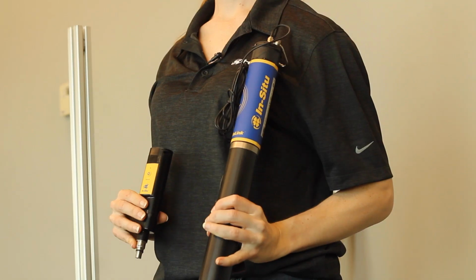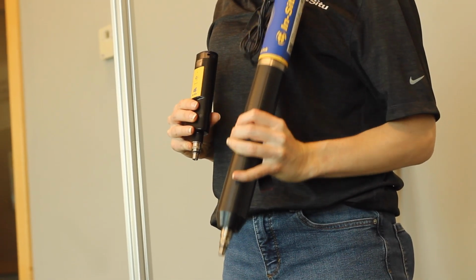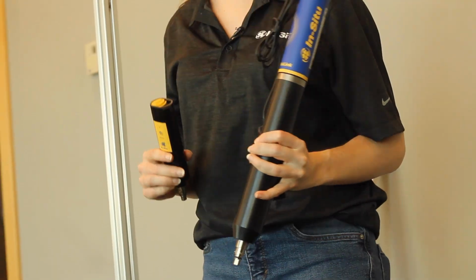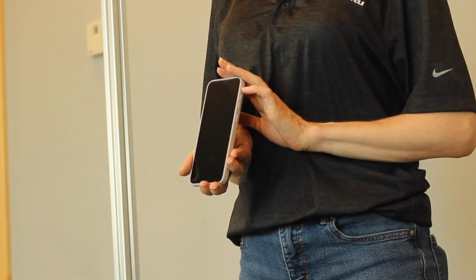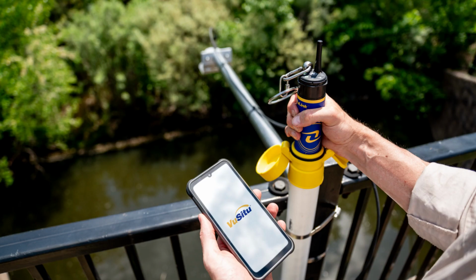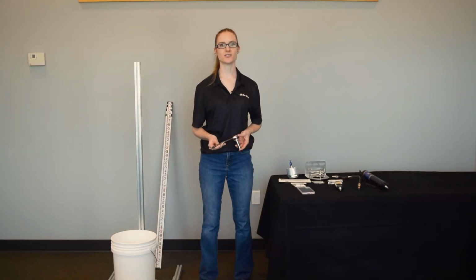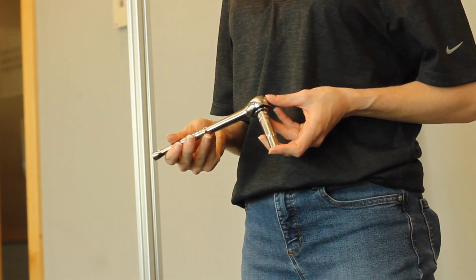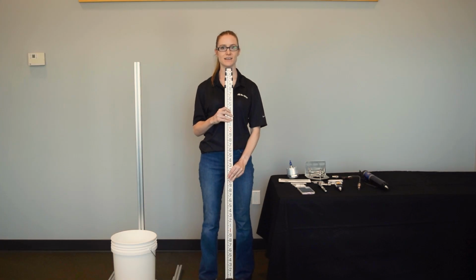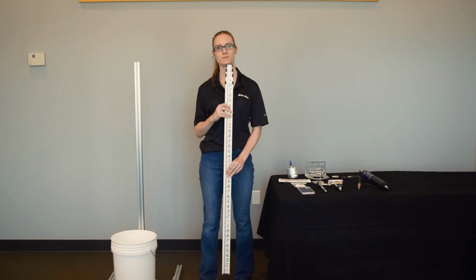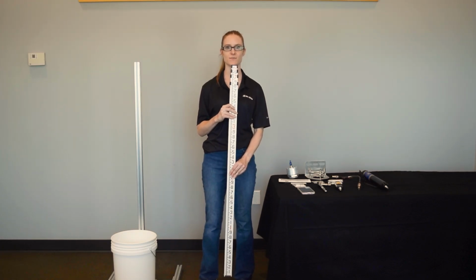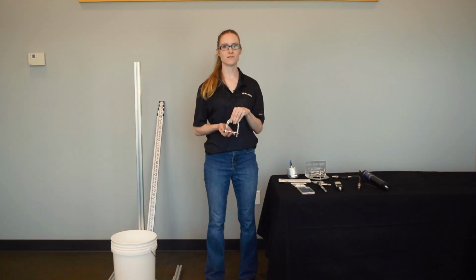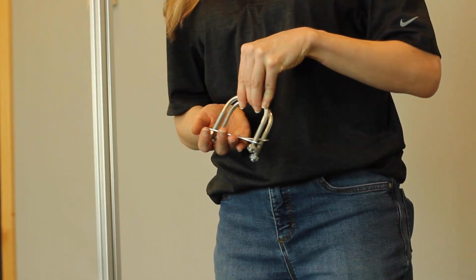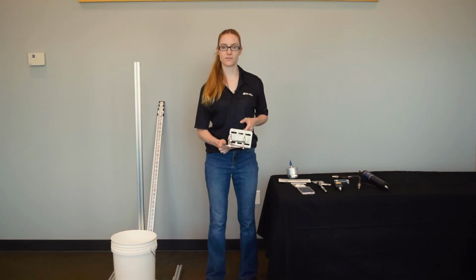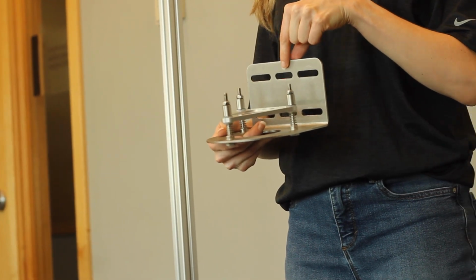You will also need a communication device, either a VuLink or a TrollCom Plus, a mobile device or tablet with the VuSitu mobile app installed, a socket wrench with a 10mm deep socket, and a level tape, stream gauge, or reference datum for collecting a manual level reference measurement. You'll also need mounting hardware for your specific deployment site that is compatible with the 3/8" slots on the mounting bracket.